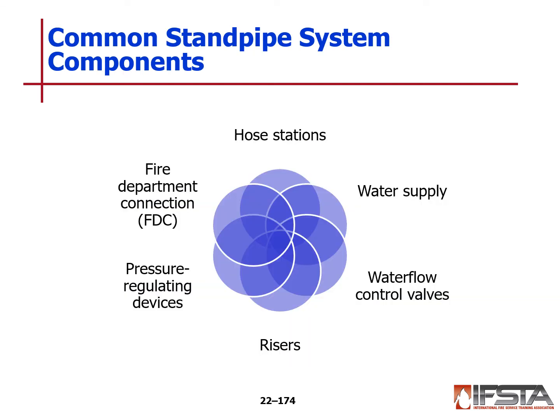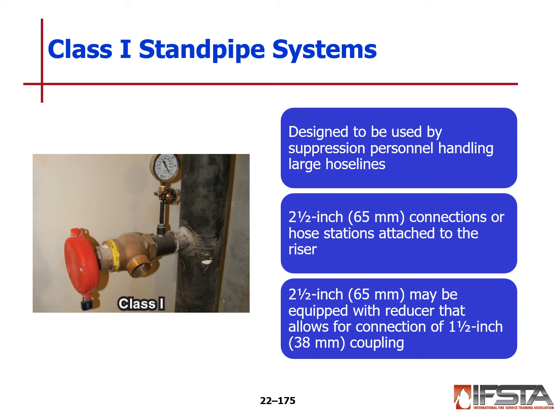Common standpipe system components: the FDC, or the fire department connection. They may have pressure regulating devices in line, risers, a water supply, may have a hose station, and water flow control valves. A Type 1 or Class 1 standpipe system is designed to be used by suppression personnel who are handling larger hose lines. Usually this is a 2.5 inch connection or a hose station attached to a riser. The 2.5 inch may be equipped with a reducer that allows for connection of 1.5 inch couplings.